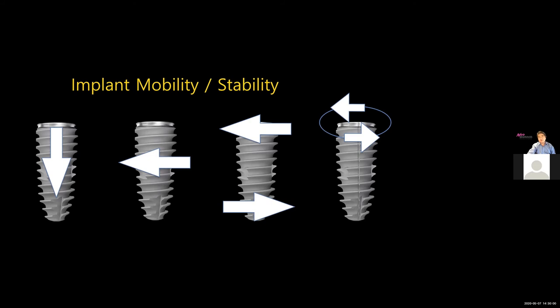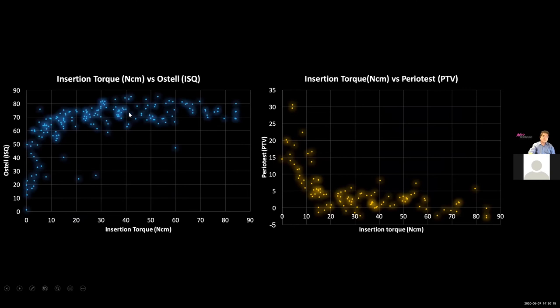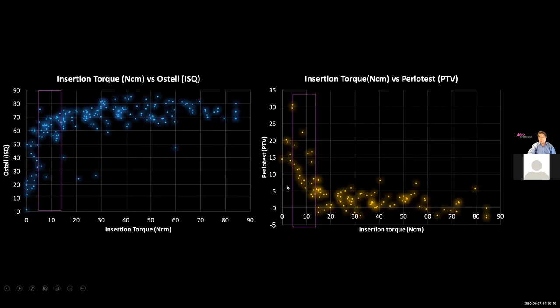The most important point is this: implant mobility — lateral movement and all types of mobility — can be measured by Anycheck and other machines, but torque itself cannot be measured by those devices. Keep in mind: a graph showing correlation between insertion torque and Osstell — if your Osstell value is 55, the insertion torque could be anywhere from 5 to 15 Ncm. Osstell will not tell you the torque value. Similarly, if your Periotest value is 7, your insertion torque could range widely — high stability value doesn't necessarily mean high torque.